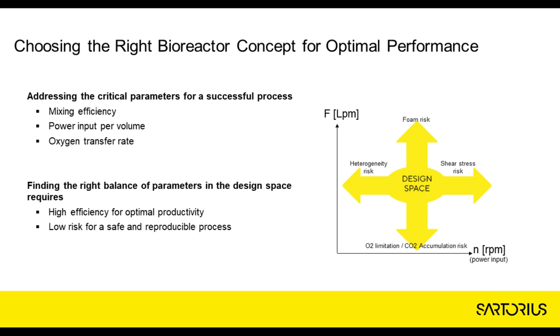If we increase too much the bioreactor agitation, for instance, in other words, the power input in the horizontal axis, we may induce shear stress. However, the design of a bioreactor needs to accommodate a minimal viable agitation in order to avoid heterogeneity risks. Alternatively, if we increase too much aeration, represented in the vertical axis in liter per minute, we may induce foam risk. However, the design of a bioreactor needs to accommodate a viable aeration to avoid oxygen limitation risks or excess of CO2 in the medium. Therefore, finding the right balance of process parameters in the design space requires high-efficient systems for optimal productivity and a low risk for a safe and reproducible process.